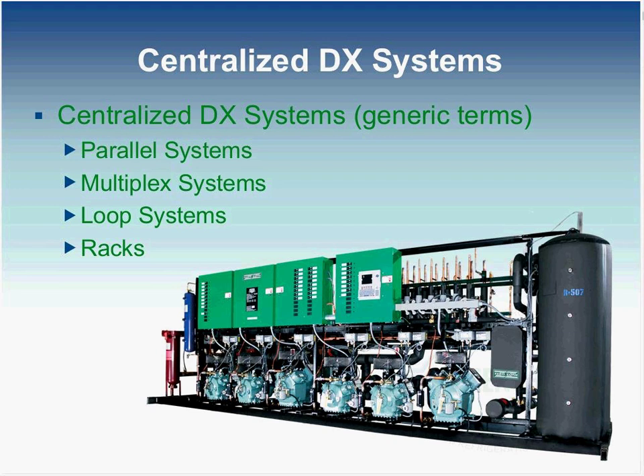Central DX systems also have some other common names. They may be called a parallel system, a multiplex system, a loop system, or probably just something as simple as a rack. What's good with these types of systems, but it's not specifically stated, is they're generally going to use an HFC refrigerant, or in old systems that are out in the field, it may be an HCFC refrigerant. The combination of having a large central system using direct expansion refrigeration out on the sales floor, having a refrigerant that's an HFC or an HCFC, makes it likelier they have a release of a large amount of refrigerant that can damage the atmosphere.